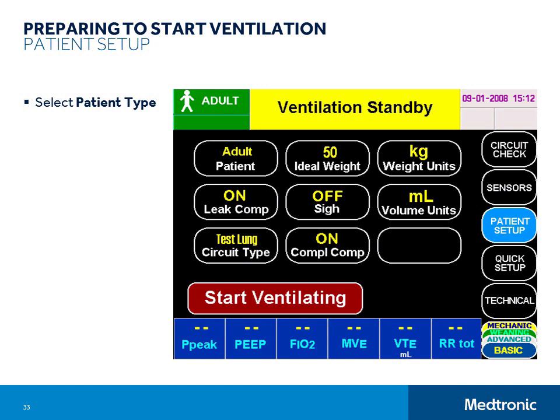Always make sure to check that the selection is appropriate. You should select Ped Infant patient category when ventilating pediatric and infant patients with 15, 12, or 10 mm ID breathing circuits, and select Adult category when ventilating adults using a 22mm ID circuit. The patient setting impacts ventilation and alarm setting ranges and ventilation management algorithms.